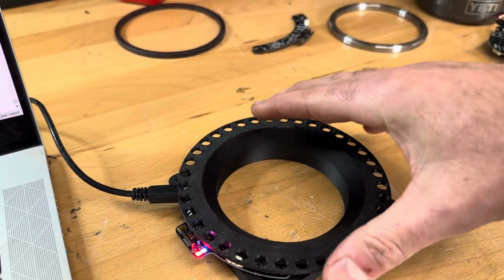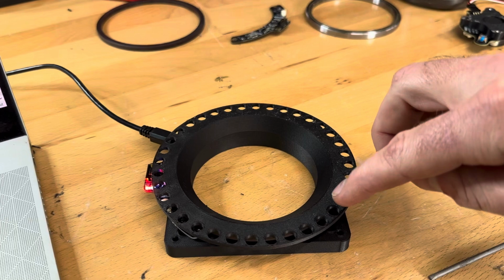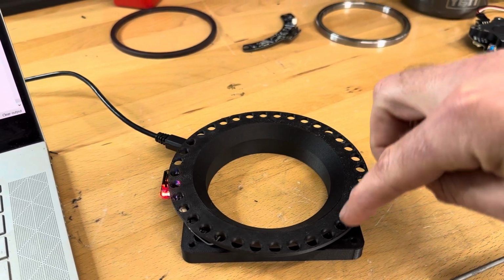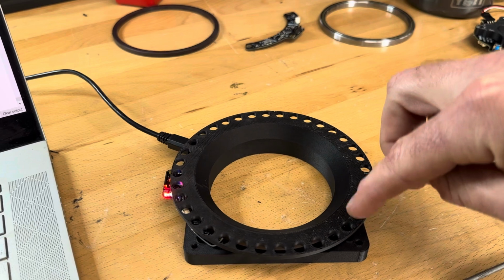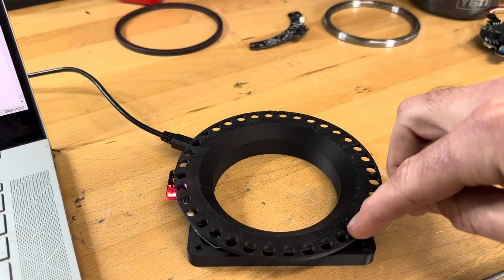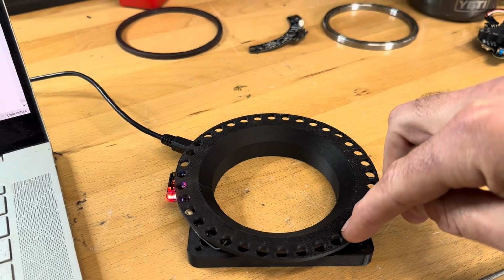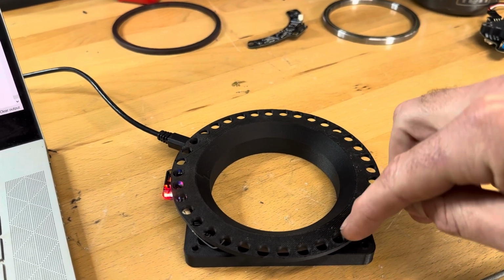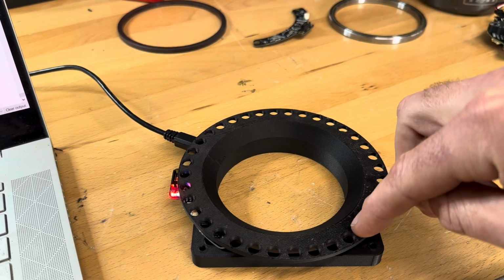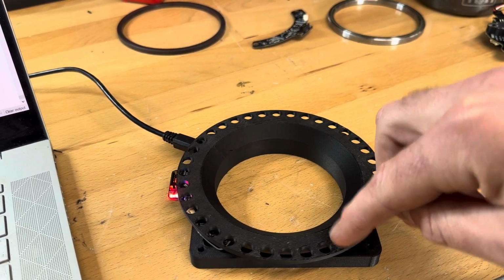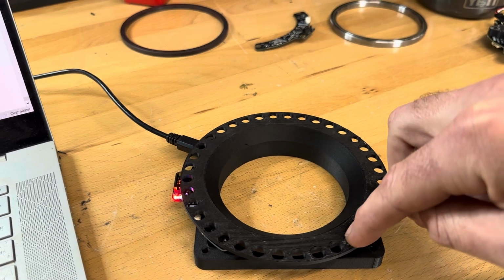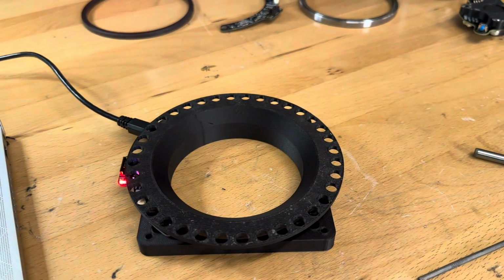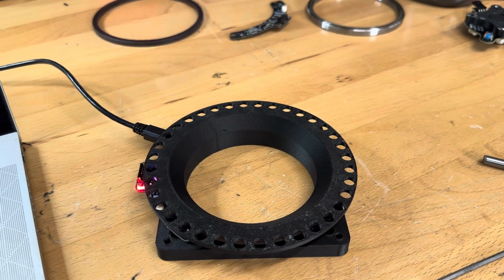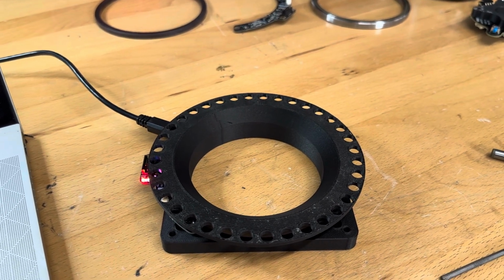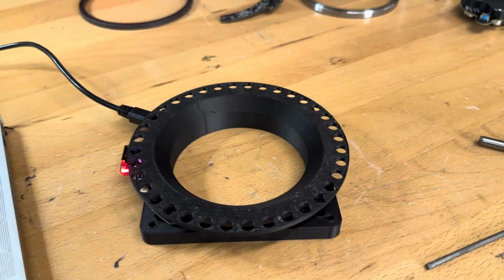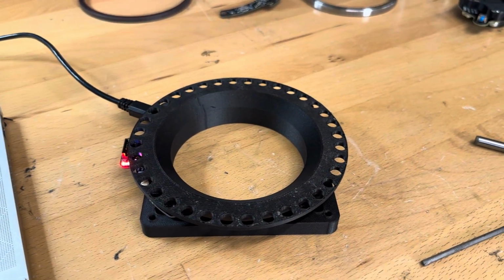It's called linearization. It's pretty simple. The way it works is you store the actual positions into the sensor in any increment you want. The sensor supports 8, 12, 24, or 36 positions. This rig's set up for 36 positions, so that's every 10 degrees. And you tell the sensor, hey, this was actually 10 degrees, and it records those values. Then you go, this is 20 degrees, records them. This is 30 degrees.